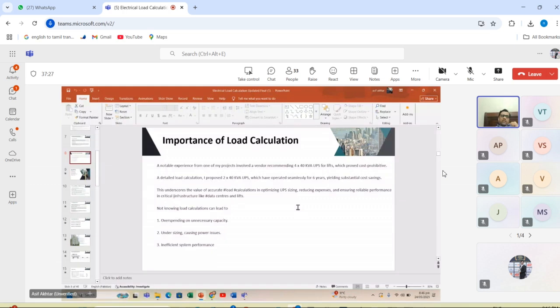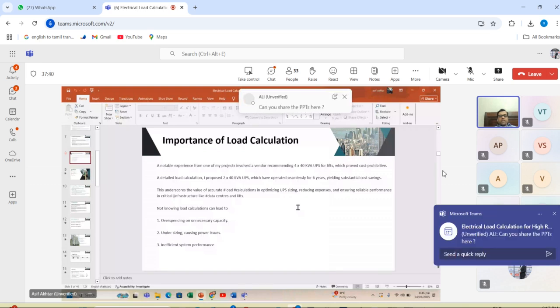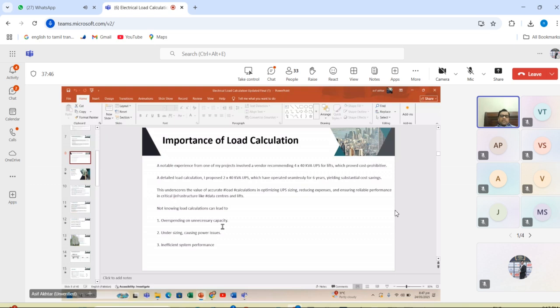So you have to do accurate load calculation. In this way, you can save lots of money for your organization. Number one, not knowing load calculation can lead to overspending on unnecessary capacity. Number two, undersizing causing power issues. And number three, inefficient system performance. If you don't do the load calculation correctly, your system will not work smoothly. So, Alhamdulillah, for the last 8 years our electrical system is working fine in our high-rise building. So, let's move on. Hope all the points have been cleared.